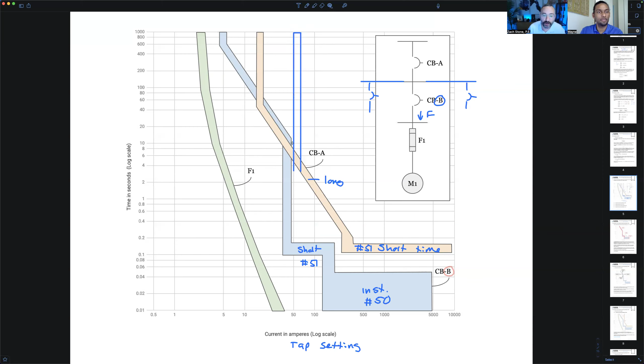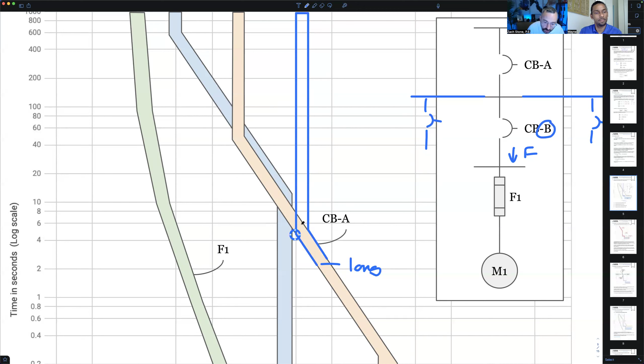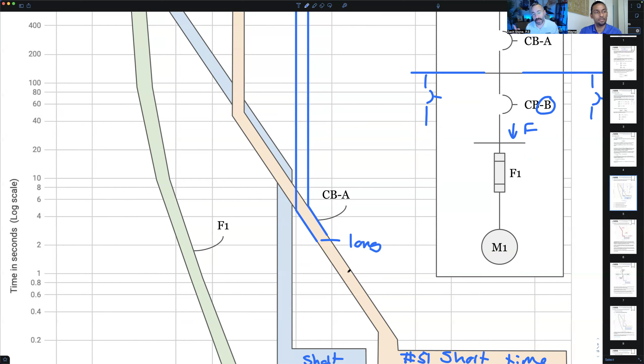Perfect. So notice how this portion of the curve doesn't change, right? It's almost like that knee point moves with the curve, this knee point right here. So if I can move it even right here, where I've got just a little bit of overlap, it would no longer be miscoordinated. And our new curve would look like this. Even just a little bit of gap here would mean they'd no longer be overlapping. But you notice here's that new knee spot. We still have that inverse shape right here, right? We've just moved the longer vertical version to the right by increasing the tap setting. Does that make sense? Yes.